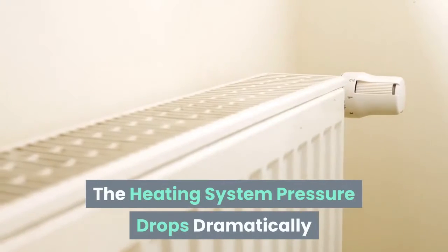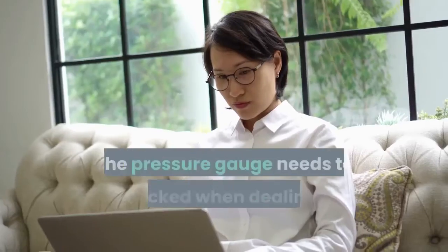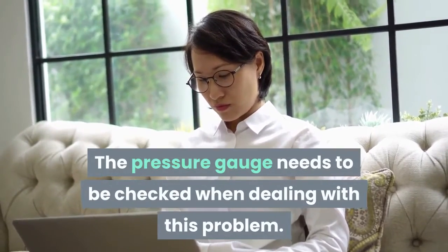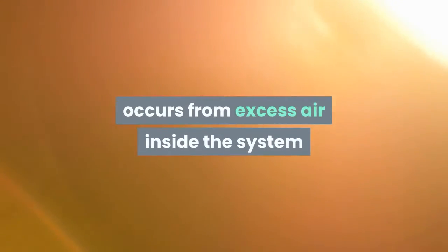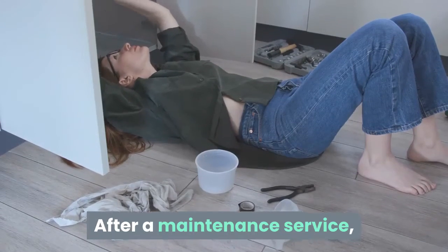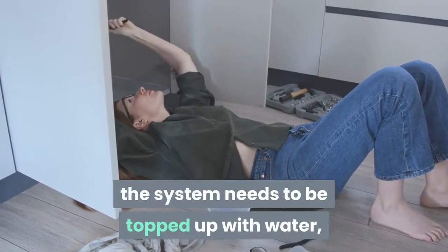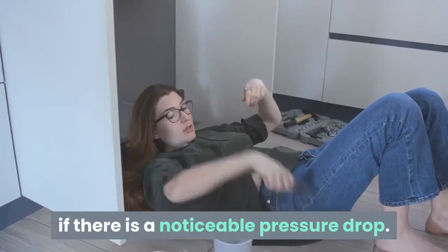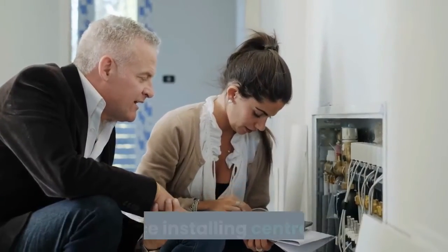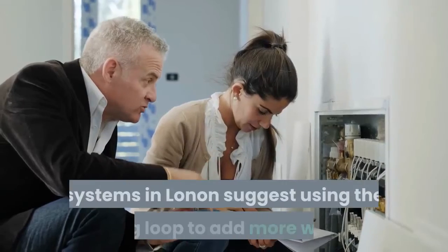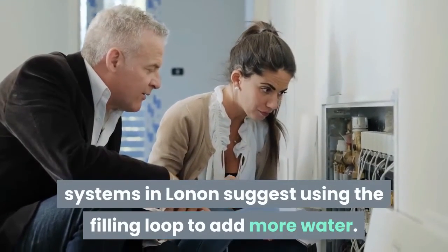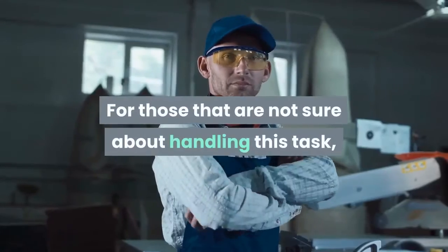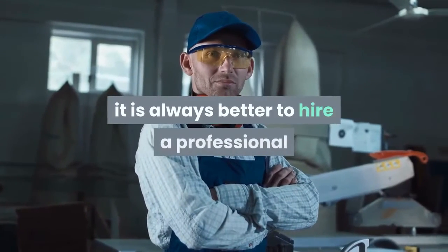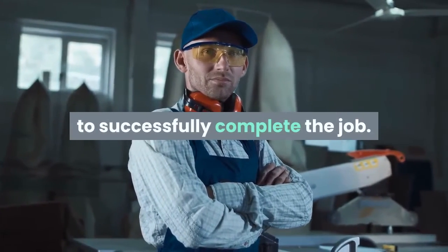The heating system pressure drops dramatically. The pressure gauge needs to be checked when dealing with this problem. There are many reasons why this problem occurs, from excess air inside the system after bleeding out the radiator to water leakages. After a maintenance service, the system needs to be topped up with water if there is a noticeable pressure drop. Expert engineers who have extensive experience installing central heating systems in London suggest using the filling loop to add more water. For those that are not sure about handling this task, it is always better to hire a professional to successfully complete the job.